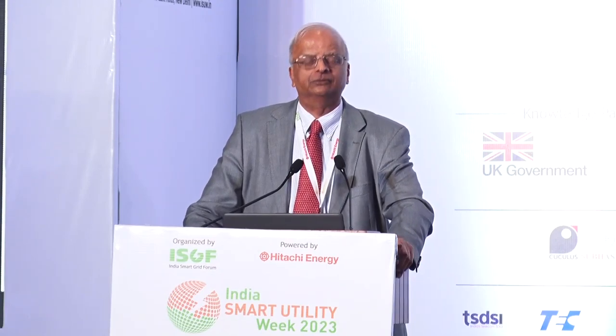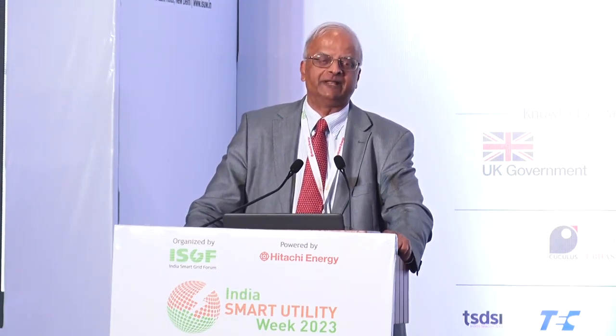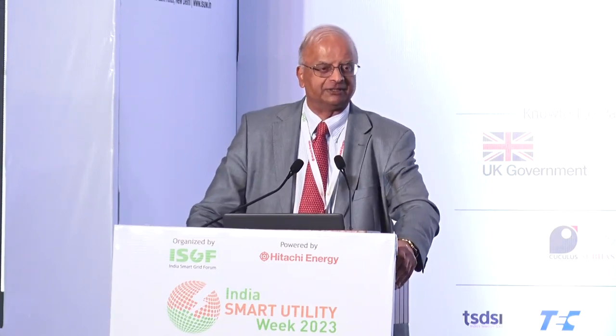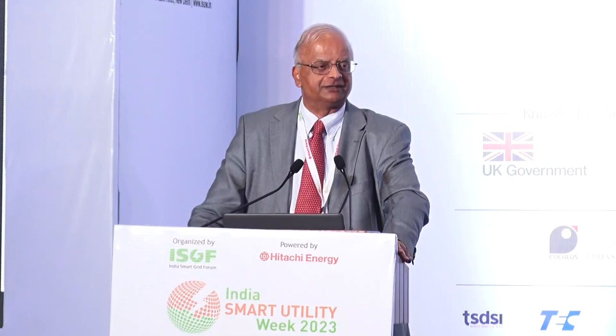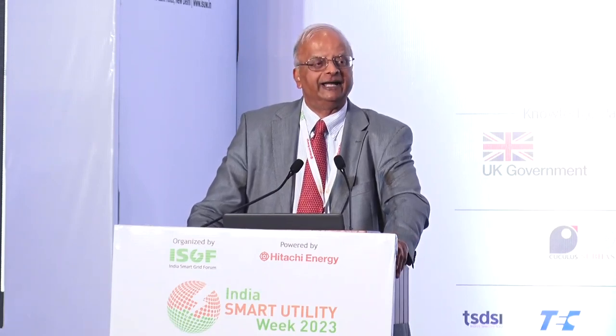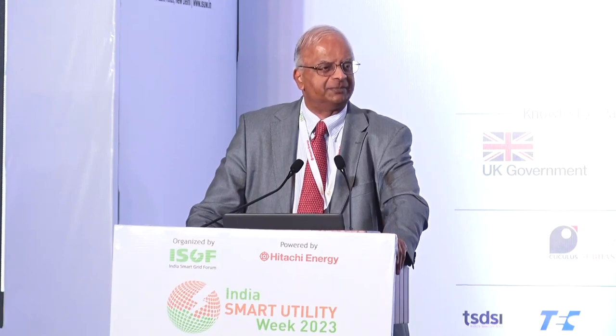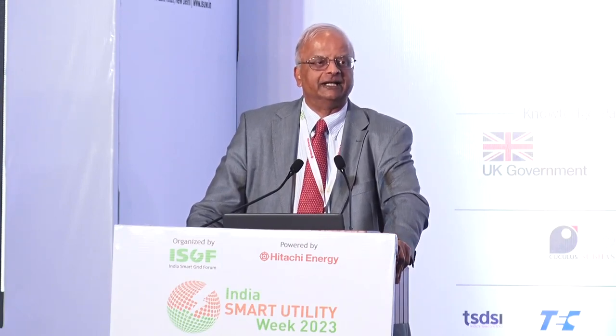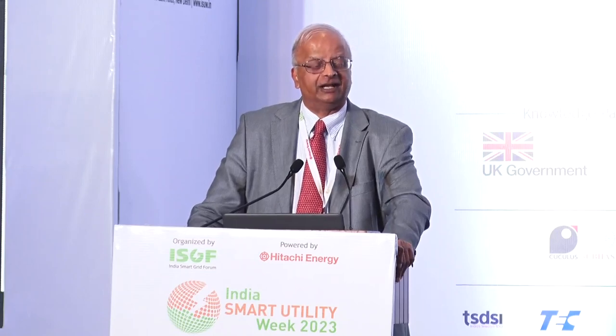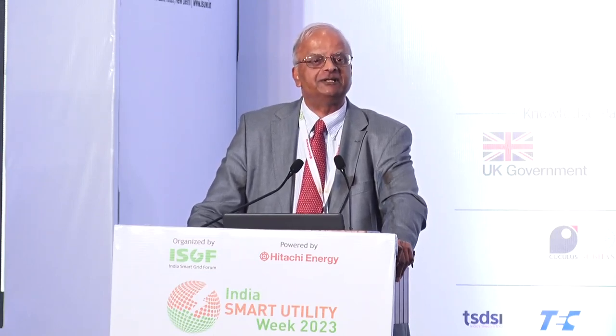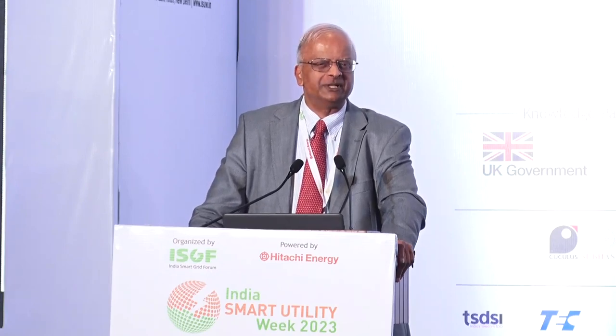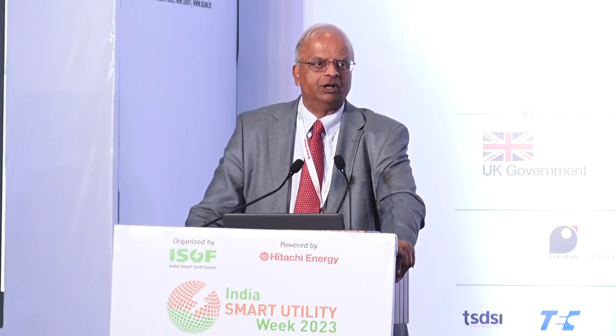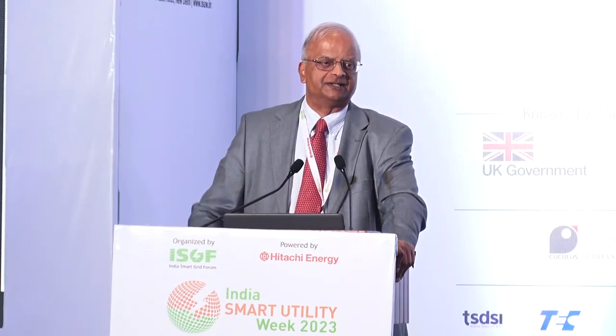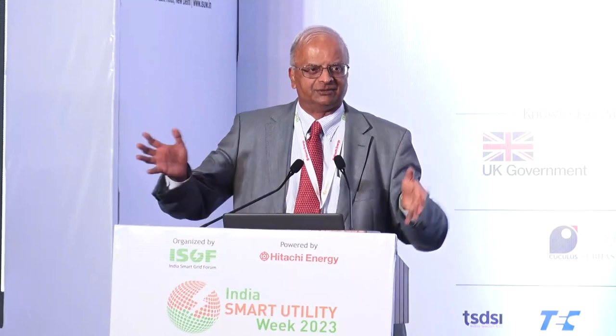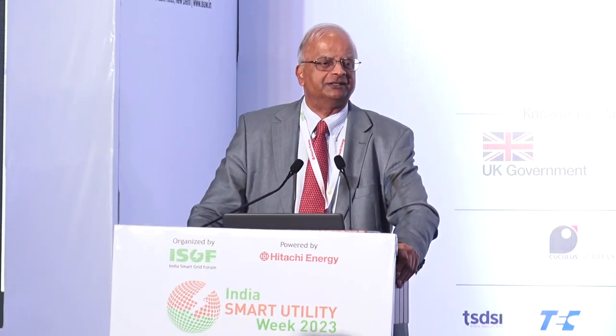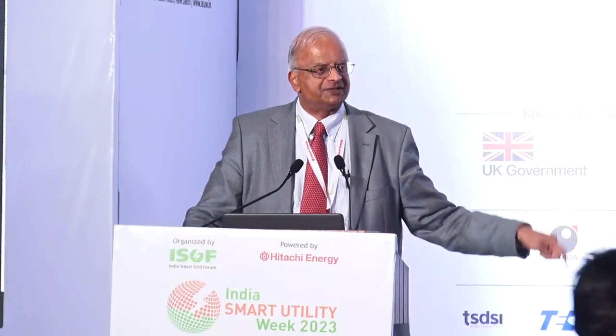That's number two. Number three: take cables. Everybody forgets about them because they're buried somewhere and nobody cares after that. If I take a 90-degree rated conductor, which is what most of us have, and add only 7 to 10 degrees to the conductor temperature, going to 102, there are reports showing the life factor of the cable decreases by 30 to 40%. So who's monitoring it? Nobody. All we have is a bunch of IEEE and other standards saying for this particular formation, derate it, do this, do that. But nobody has really paid attention to today's scenario for a cable that was purchased 40 years ago.